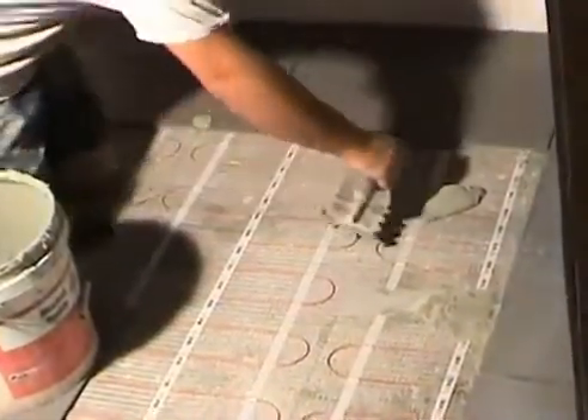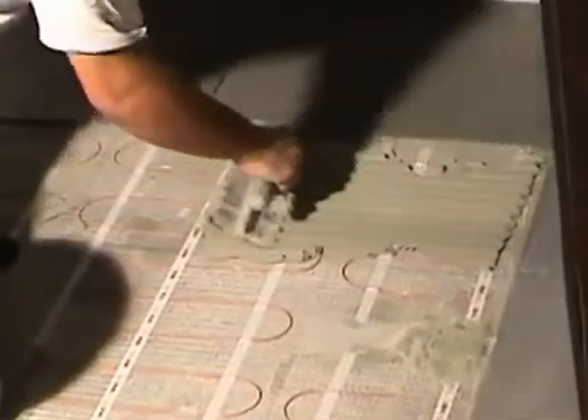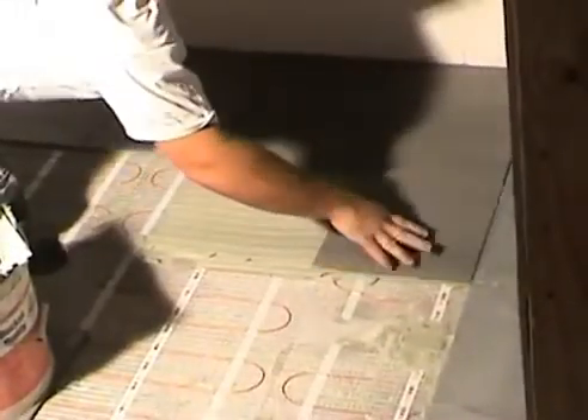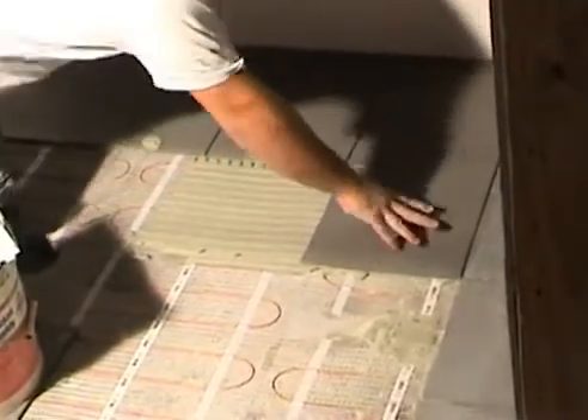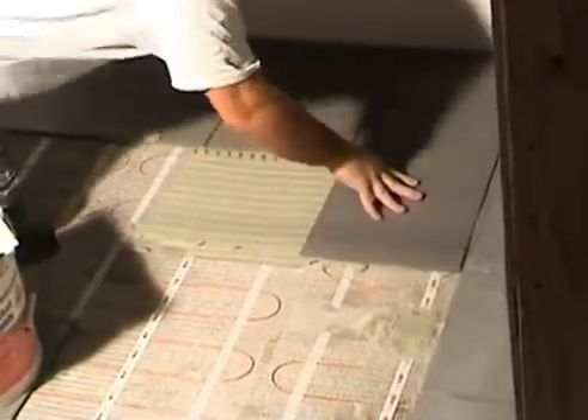Spread a moulding compound over the mat using a rubber filling knife. Ensure the mat is completely covered and that there are no air pockets. The tiles can be laid directly over the mat using a flexible tile adhesive, but care needs to be taken not to damage the cable. The tile adhesive must be approved for the floor heating by its manufacturer.